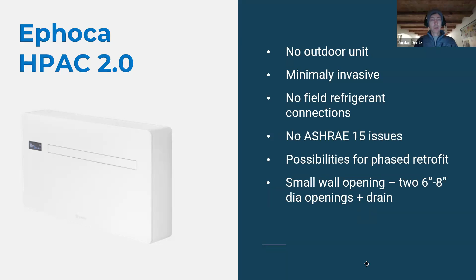We demonstrated this product in an apartment in a building in Queens, New York. You can see the building on the upper left. We did one apartment to start off with. In this case, we used an existing air conditioner sleeve to install the heat pump, using the opening of the sleeve for exchanging air with the outdoors for the heat pump's outdoor unit, which is inside the unit in the apartment. You can see the floor plan on the right, where the yellow stripes show where those units are installed.